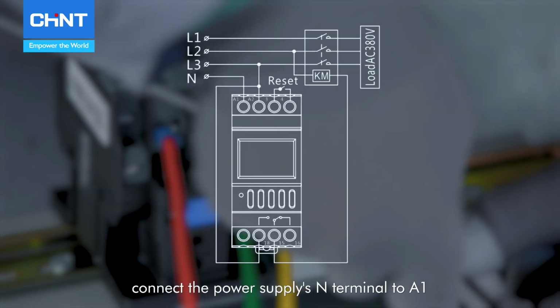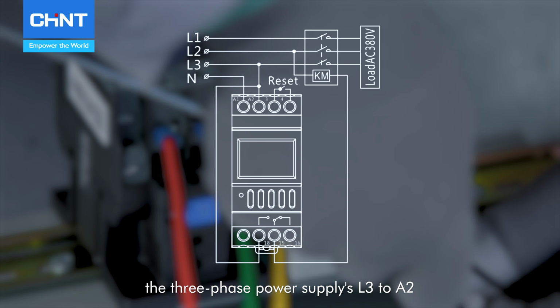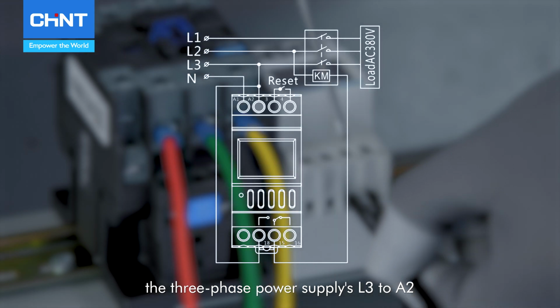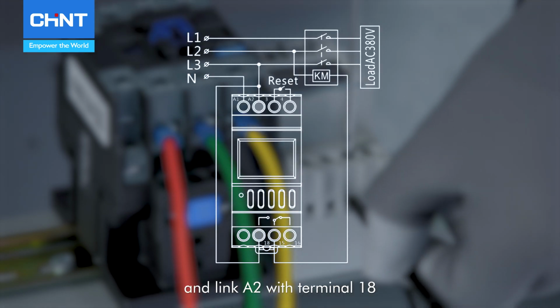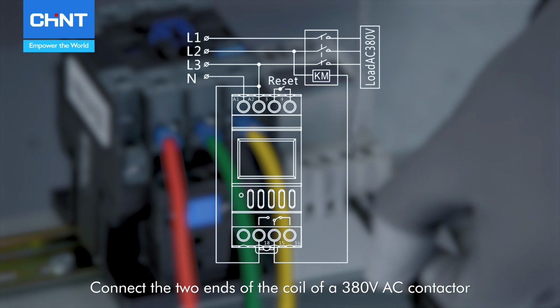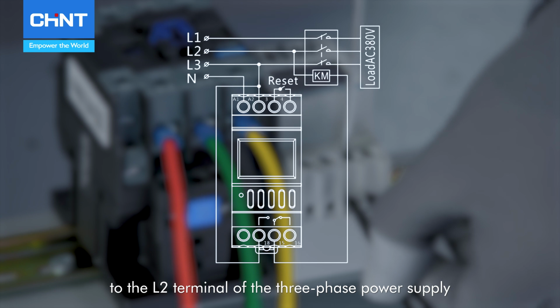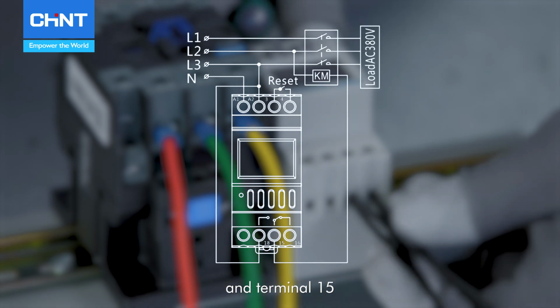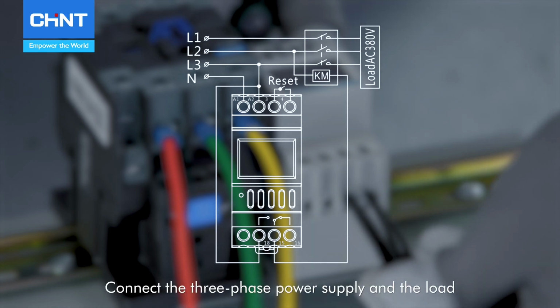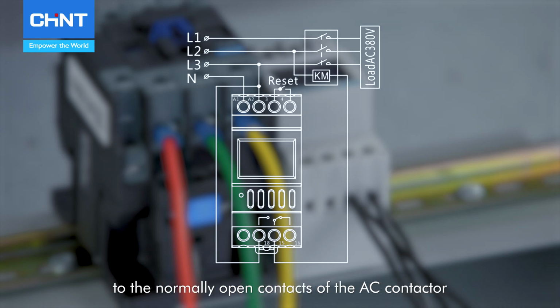Connect the power supply's N terminal to A1, the 3-phase power supply's L3 to A2, and link A2 with terminal 18. Connect the two ends of the coil of a 380 volts AC contactor to the L2 terminal of the 3-phase power supply and terminal 15. Connect the 3-phase power supply and the load to the normal open contacts of the AC contactor.